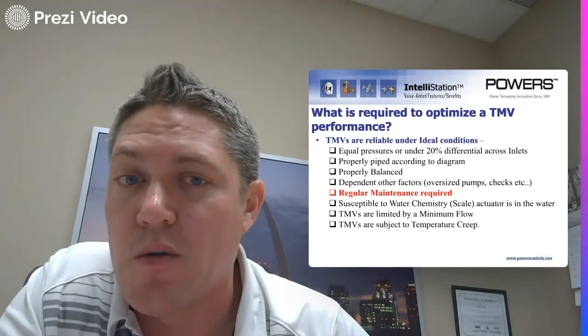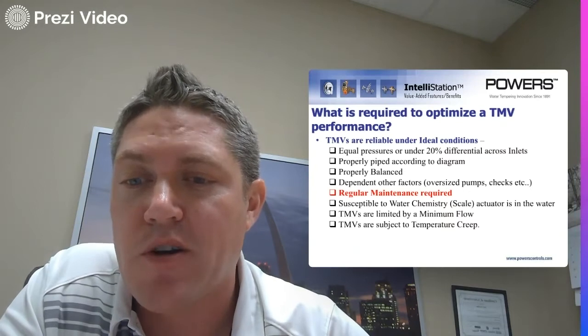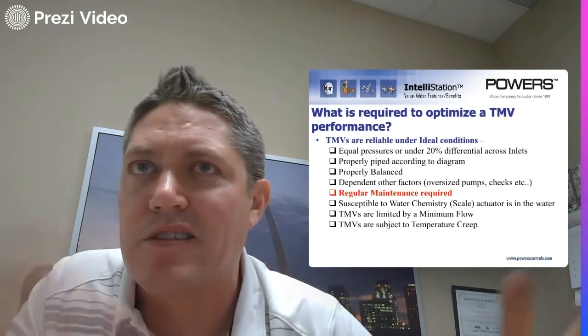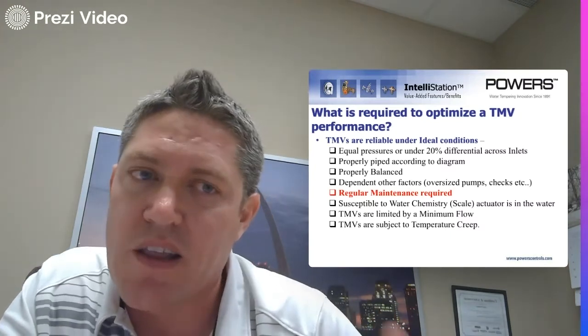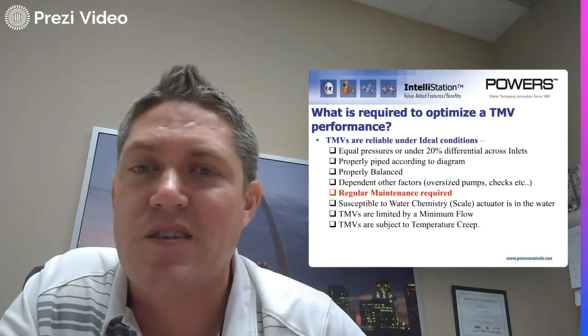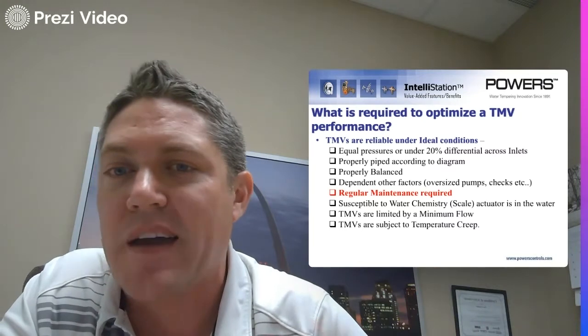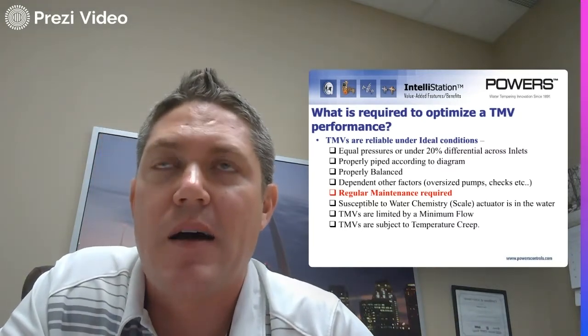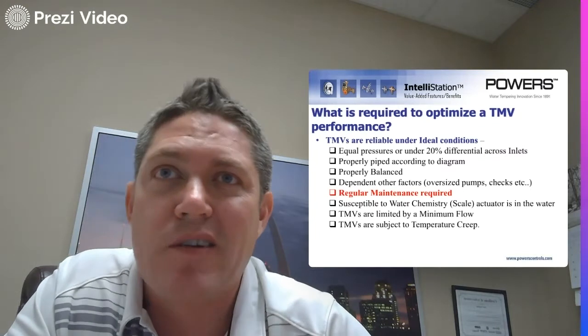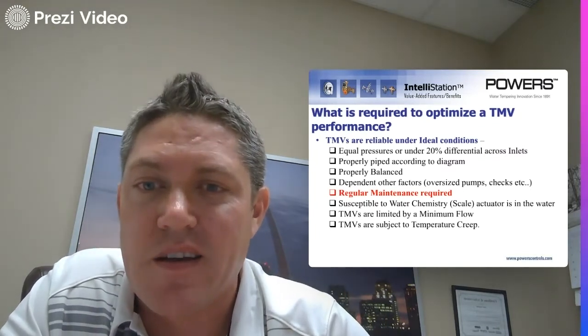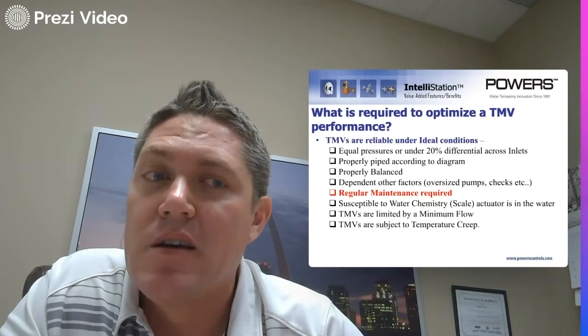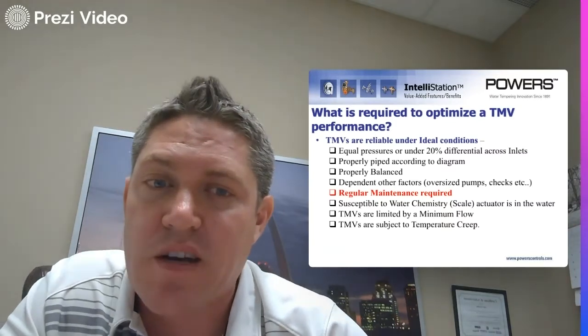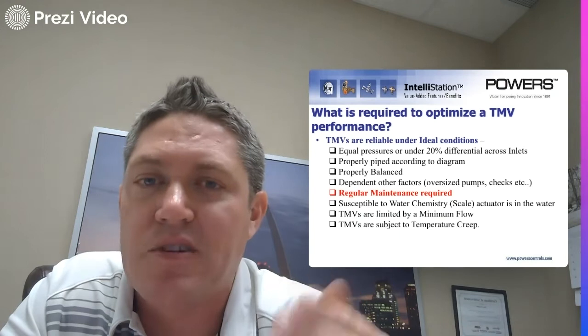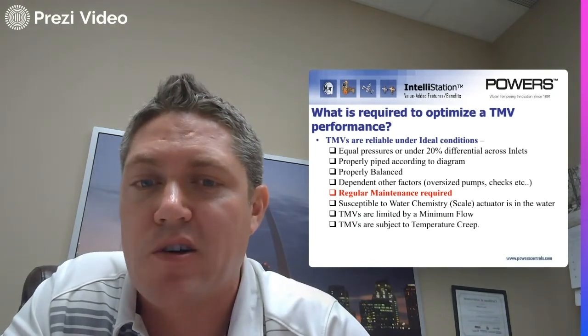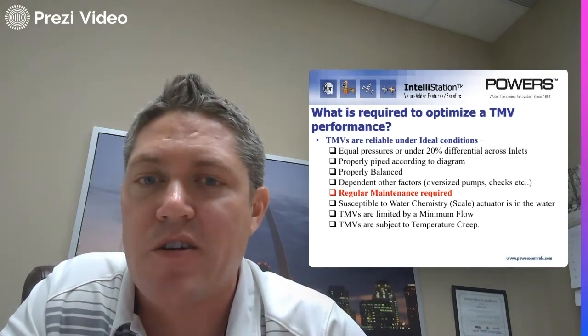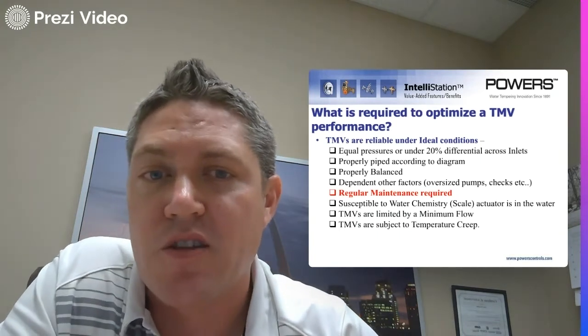So that's where you put in a balancing valve on that return piping, so that you choke it down to say maybe 95% closed. So it's only allowing 5% to go through that balancing valve and back to the heater, the other 95% back into the cold inlet of the mixing valve. Maybe that's too much. Maybe it needs to be choked down to 97, 98%. Or maybe it's not enough. Maybe it only needs to be 90% choked down and allow 90% of the return water to go back to the cold inlet and 10% back through the heater to be reheated and make up that heat loss on the loop.